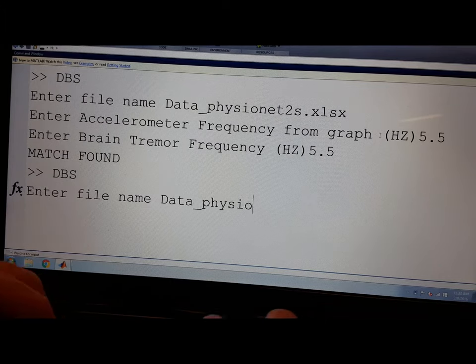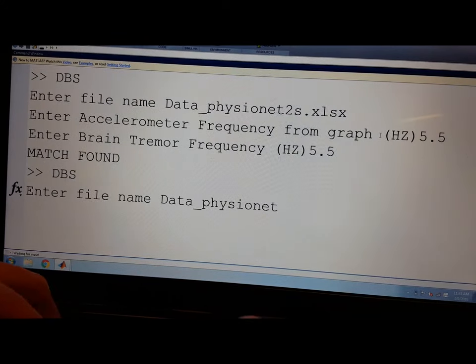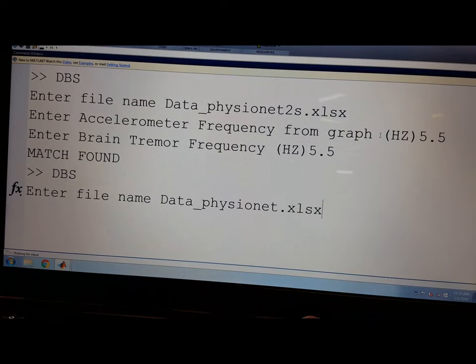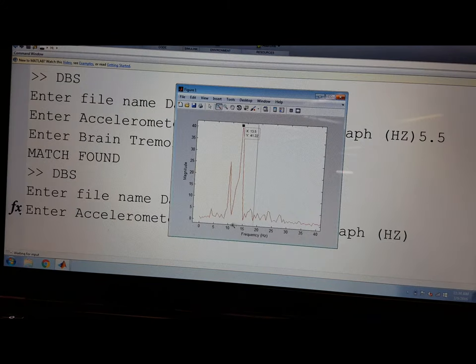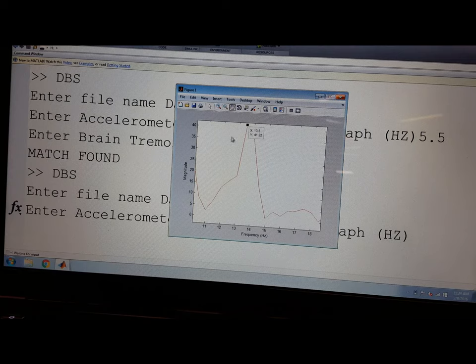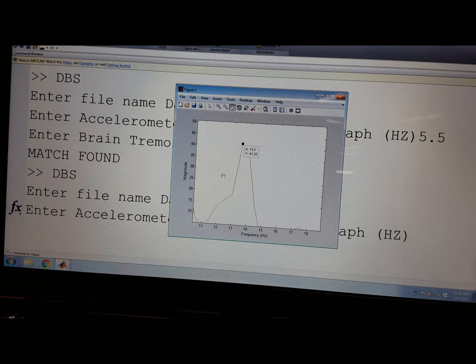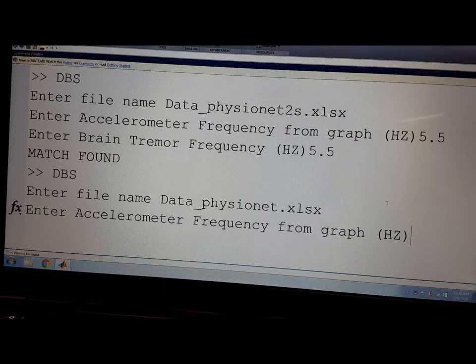If the two frequencies are within tolerance, then the program will display a match has been found. If the software displays a match has not been found, the surgeon will be prompted to move the microelectrode to a new position.